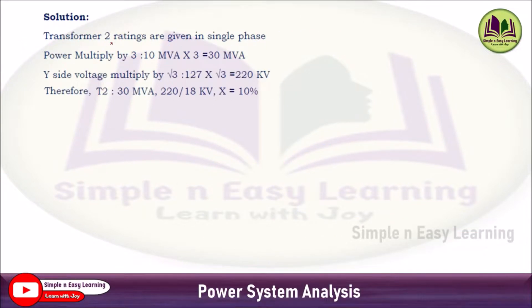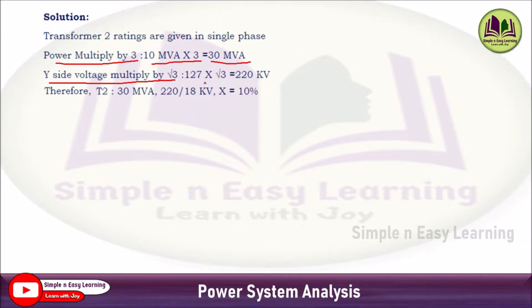For transformer T2, ratings are given in single phase, so you need to multiply the power by 3. Power rating is 10 MVA per unit, with three units, giving 30 MVA. For the star side voltage, multiply by root 3: 127 × √3 = 220 kV. Therefore, the transformer rating becomes 30 MVA, 220/18 kV, x = 10%.